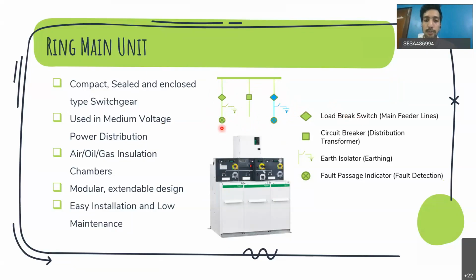Plus, one more device called a fault passage indicator is also attached to these limbs. What this fault passage indicator does is help in fault detection. Whenever fault current passes through it, it will immediately blink or give some indication to the control center saying that a fault has passed through that particular location. So locating a fault becomes very easy with this device. We'll see in more detail how that is done.